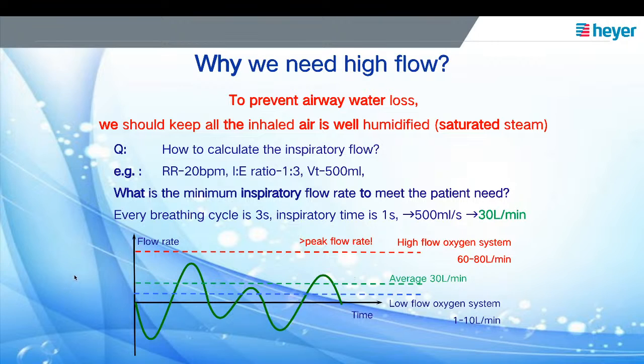As we know, the peak flow rate of the patient will be much higher than the average flow rate. So the peak flow rate is usually much higher than 30 liters per minute. So the high flow oxygen system should give 60 to 80 liters per minute. Our regular oxygen system only provides a low flow rate of oxygen, about 1 to 10 liters per minute. We know this is far from enough to meet the patient's need.